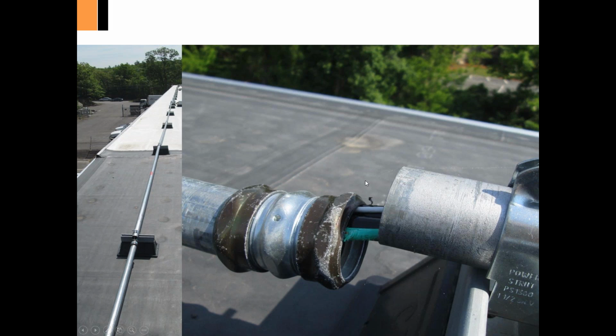There's another situation probably about 10 years ago in Bakersfield, California, where there was an incident very similar to this, but with very unfortunate results. You could look that up online. But basically, that was kind of the first of the learning experiences that this type of metal raceway needed those fittings. So there was a fire incident in that particular case. So again, that's a design issue, and we would also catch this during inspection or commissioning as well.